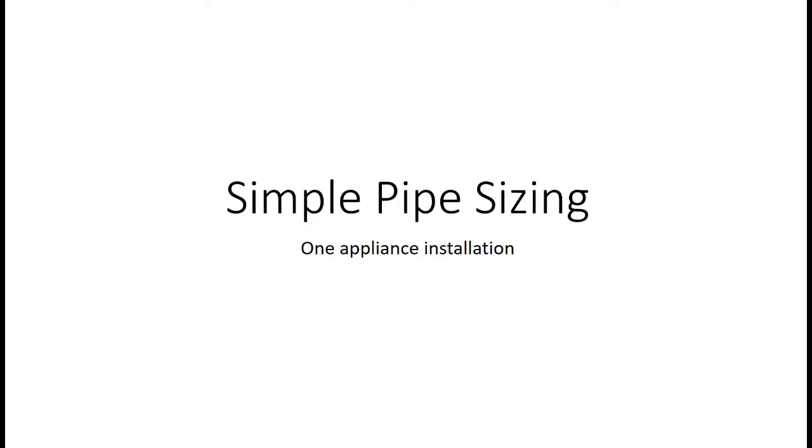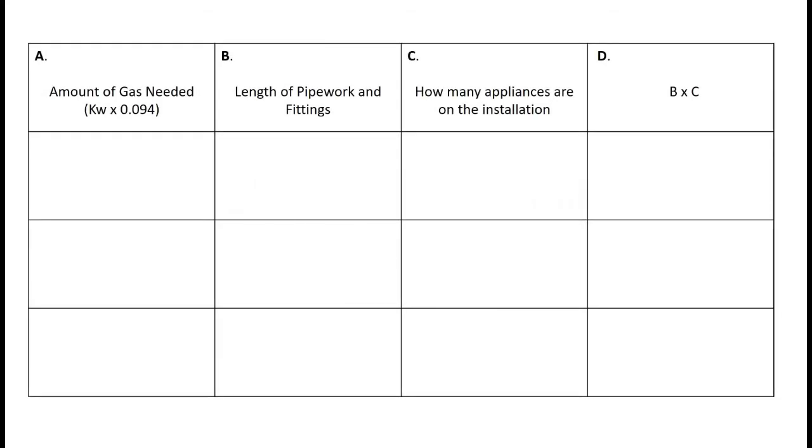The first thing I do is draw a box with four columns and three rows. At the top I put the amount of gas needed in box A, length of pipework and fittings in box B, how many appliances are on the installation in box C, and for box D we're going to multiply the number B by C.